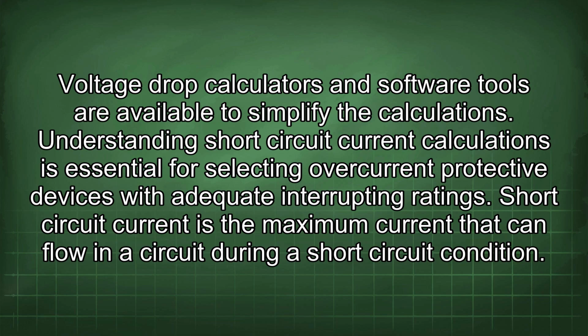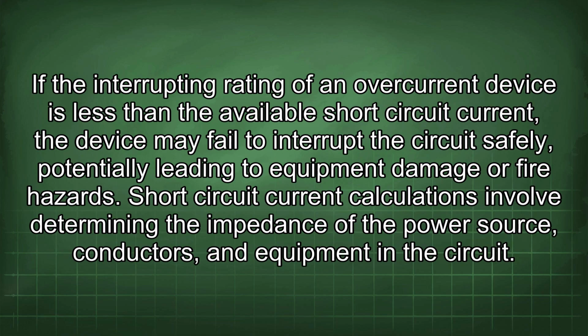Understanding short-circuit current calculations is essential for selecting overcurrent protective devices with adequate interrupting ratings. Short-circuit current is the maximum current that can flow in a circuit during a short-circuit condition. If the interrupting rating of an overcurrent device is less than the available short-circuit current, the device may fail to interrupt the circuit safely, potentially leading to equipment damage or fire hazards.